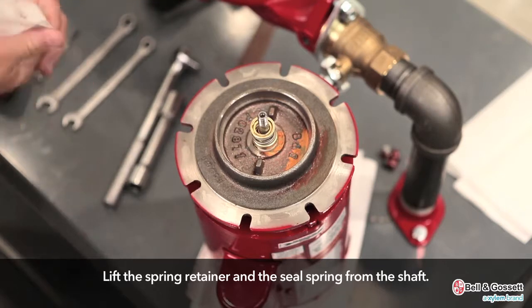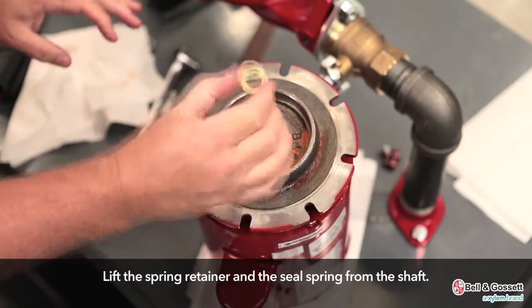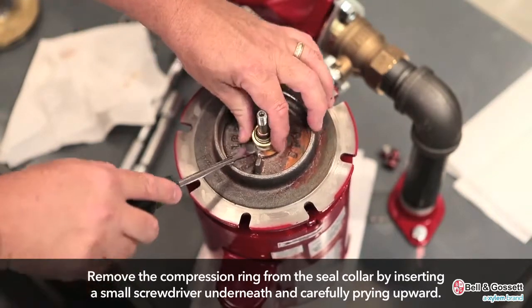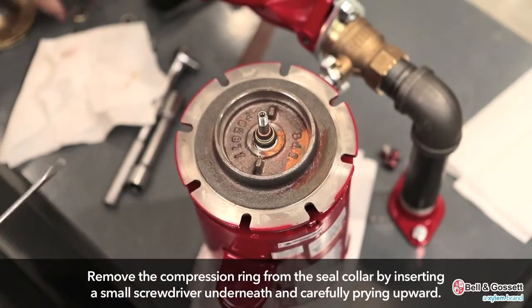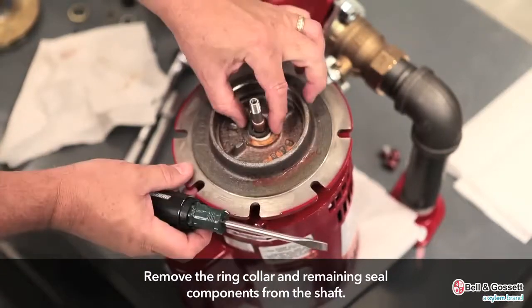For all except the 1.25 inch or 3.18 cm seal assembly, lift the spring retainer and the seal spring from the shaft. Remove the compression ring from the seal collar by inserting a small screwdriver underneath the ring and carefully applying an upward force. Remove the ring collar and remaining seal components from the shaft.